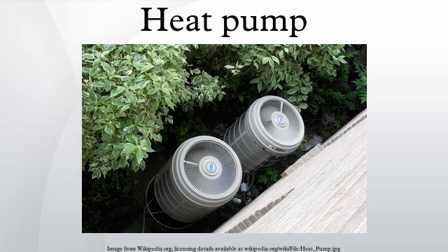The refrigerant then returns to the compressor and the cycle is repeated. It is essential that the refrigerant reaches a sufficiently high temperature, when compressed, to release heat through the hot heat exchanger. Similarly, the fluid must reach a sufficiently low temperature when allowed to expand, or else heat cannot flow from the ambient cold region into the fluid in the cold heat exchanger.